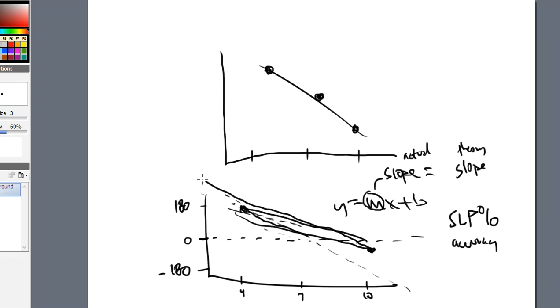So what would happen is that number would be skewed off from the rest, and I would not know any different, but there's a chance that my pH buffer is wrong, because maybe it's not shelf stable. Maybe it's going to give me a weird number over the course of time. And that's very, very, very common, especially with pH buffer of 10. So I would not know this, and I would not catch it if it wasn't for a 3-point calibration, because a 3-point will help me keep myself in line to make sure it's reading the best way possible.